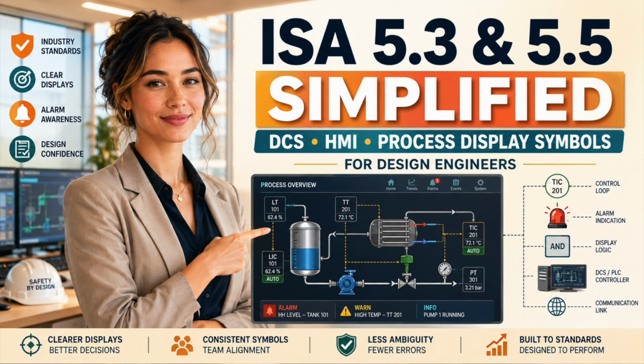The equipment or control detail display should expose controller modes, valve states, permissives, interlocks, sequence status, and diagnostic information. Engineering and maintenance screens may then provide raw input and output status, device diagnostics, detailed logic, communication health, overrides, and configuration information. When every screen becomes a detail screen, hierarchy disappears and the operator is forced to search.